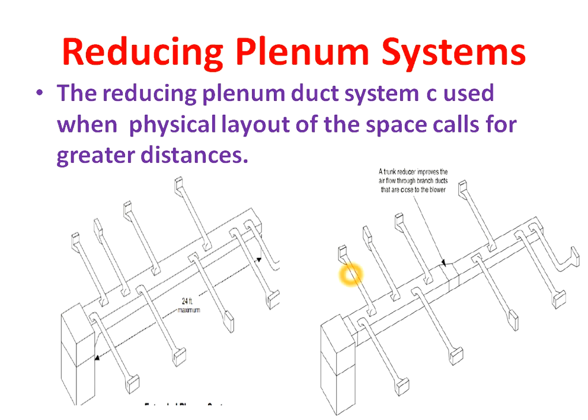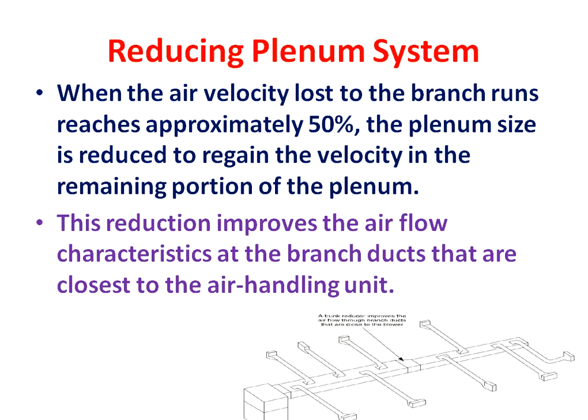We will now see in detail how we achieve this. This is the diagram of the reducing plenum system and how we reduce the duct. Suppose these are the branch ducts and this is the main duct. If the velocity in a branch duct is near 50% of the main duct velocity, then we reduce the cross-sectional area of the main duct. Due to this reduction in cross-sectional area, there will be proper balancing of air in all the branch ducts.